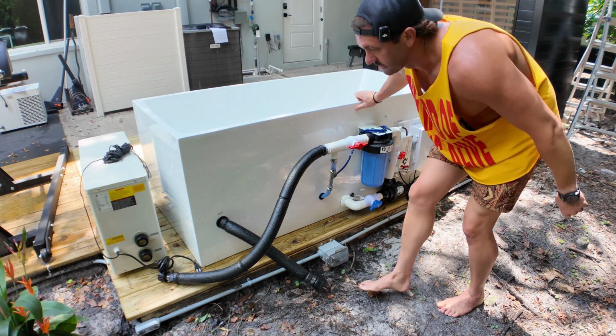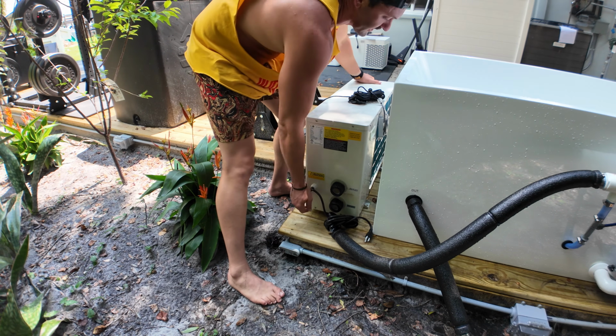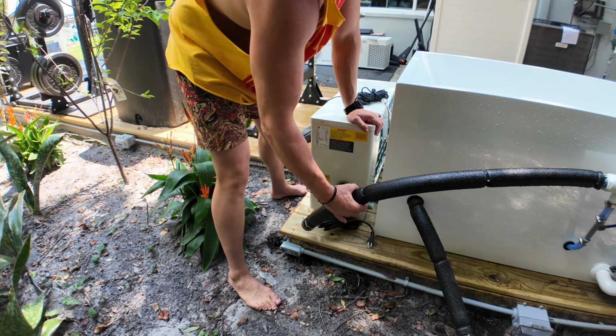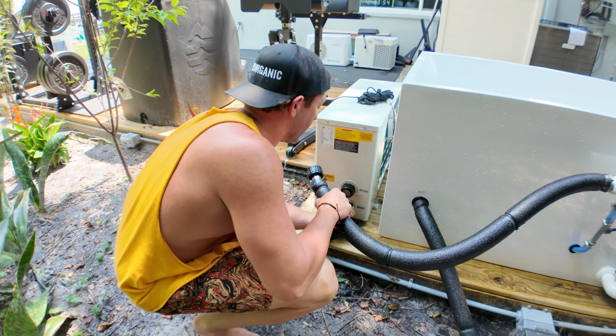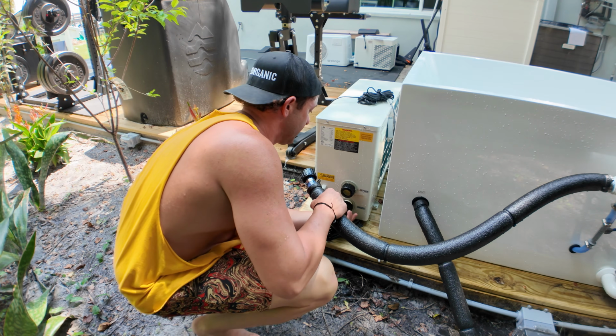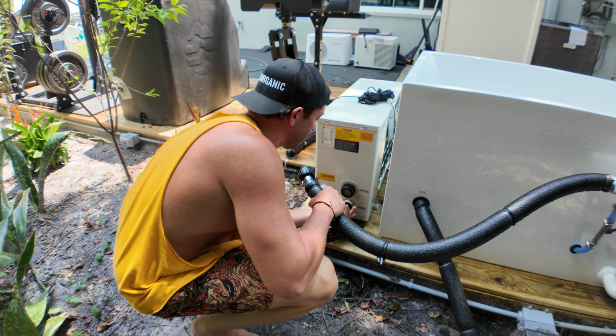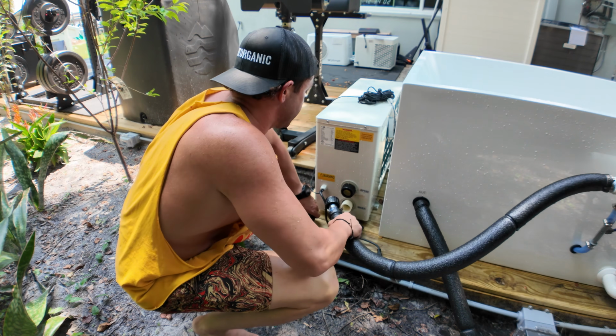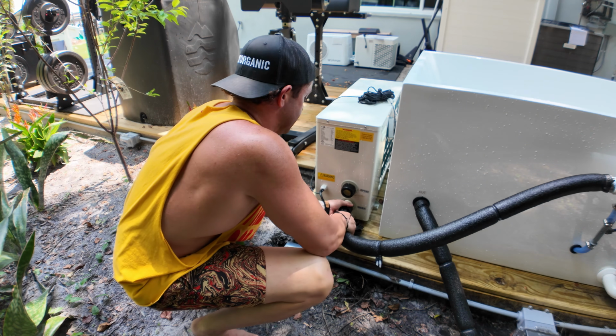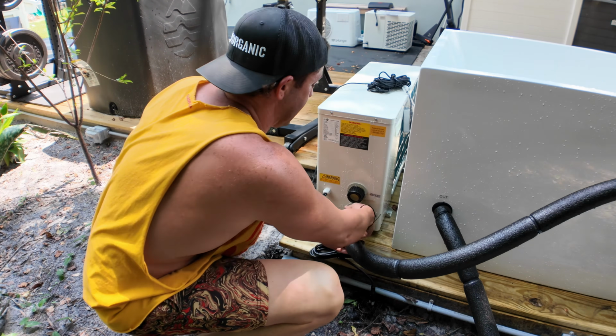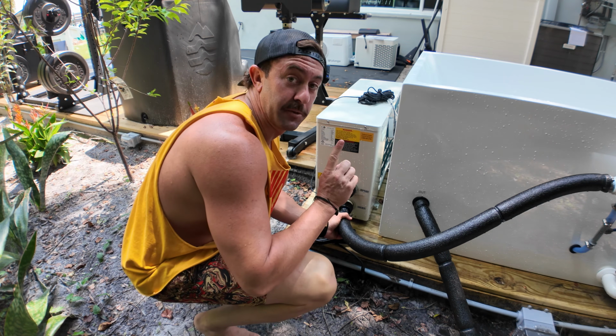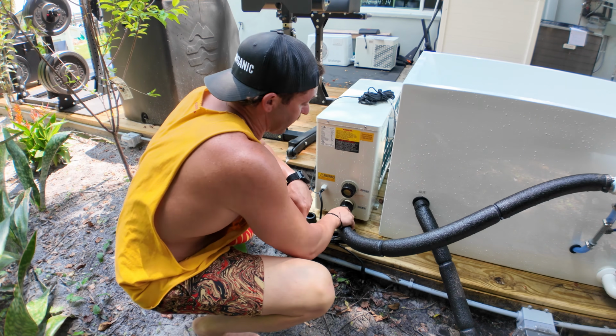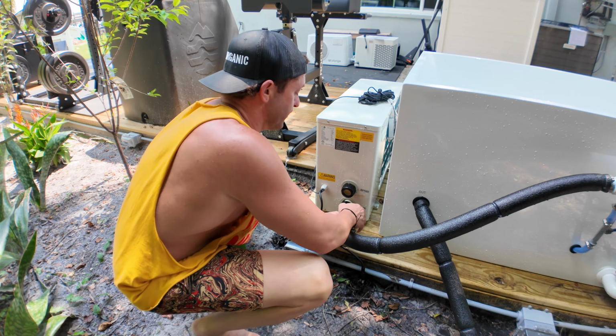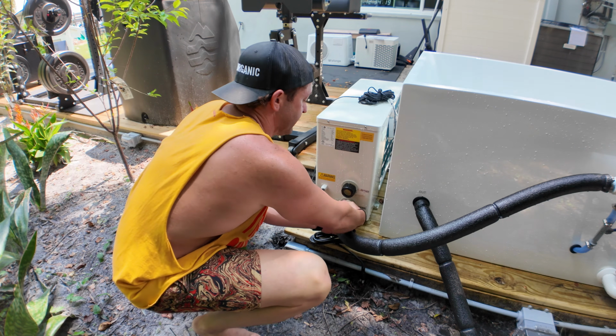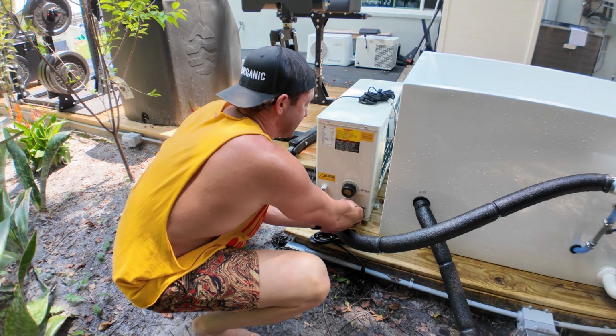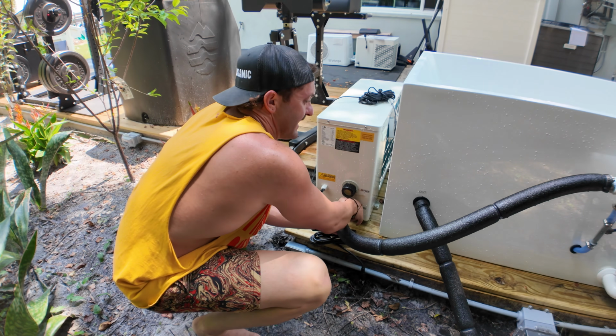Now let's go ahead and connect it to the chiller. Pretty easy — all you're gonna do is put your chiller off to this side where these tubes go. The top tube is the in, and that's where the water is actually gonna be going into the chiller. You're gonna unscrew this little cap that comes with it to keep it safe from cracking during shipping, and put this tip, the in, onto the inlet. You want to make sure this is tight, but here's a little piece of advice: sometimes this can get a little wedged inside the cap, so pull the tube out, not hard, just to make sure it's not getting wedged inside there so you don't have any leaks. Then tighten it all the way down.